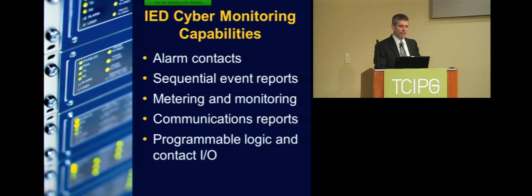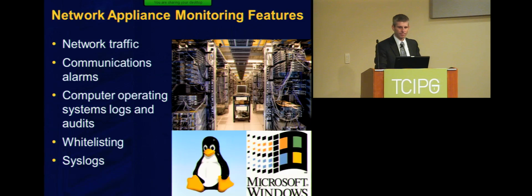And then finally, the devices these days are very, very flexible. So we can make essentially security alarms, if you will, customized ones by using programmable logic and contact I/O. So I can say, if the door is open and nobody gave us permission from, say, the operations center, I could lock down ports or something like that. So there's a lot of flexibility that we can use to tailor a custom profile inside these IEDs with this programmable logic. At the network appliance level, we have, well, certainly network traffic monitoring.